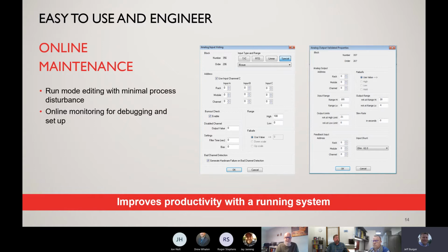So there are a lot of different PLCs and a lot of different manufacturers that will actually require you to do a cold start, which then takes down the whole process, and you'll have to shut down your system, and then you'll start it back up, and that requires some downtime there. So this is a very important good tool within the HC900 that allows you to do configuration changes and go to a hot start.